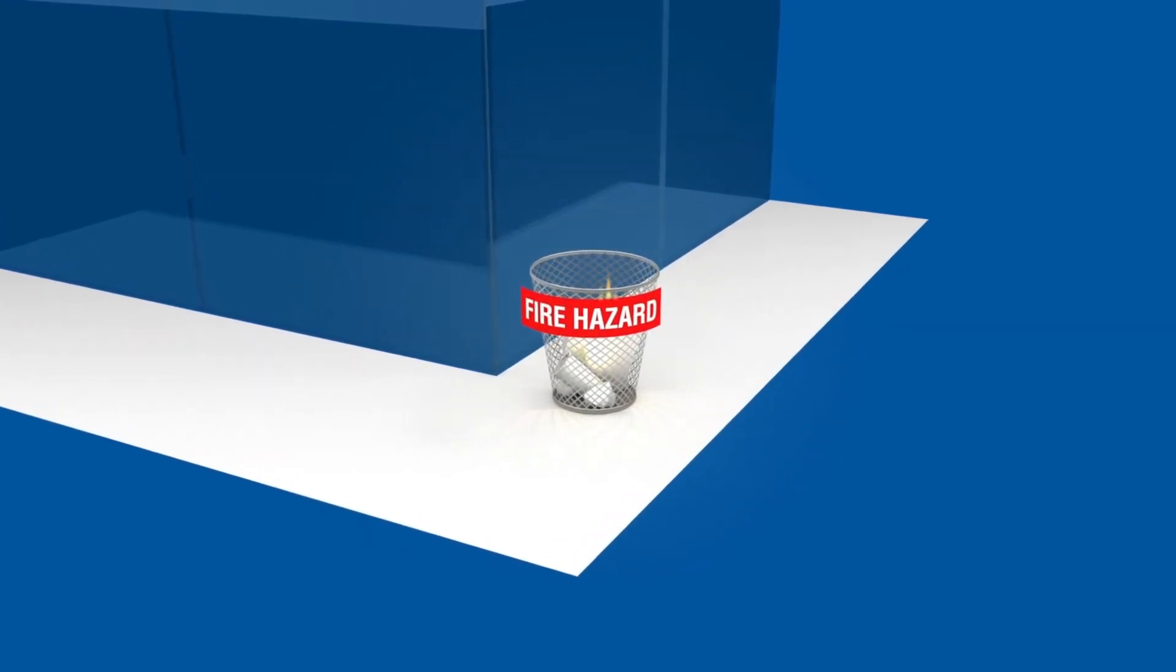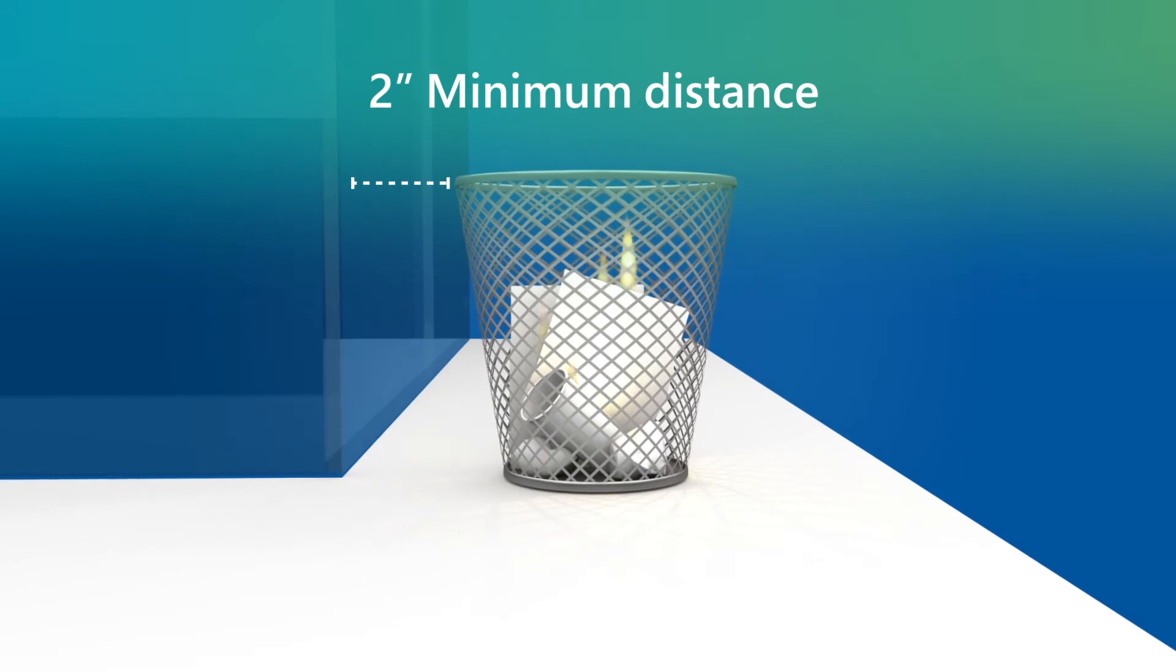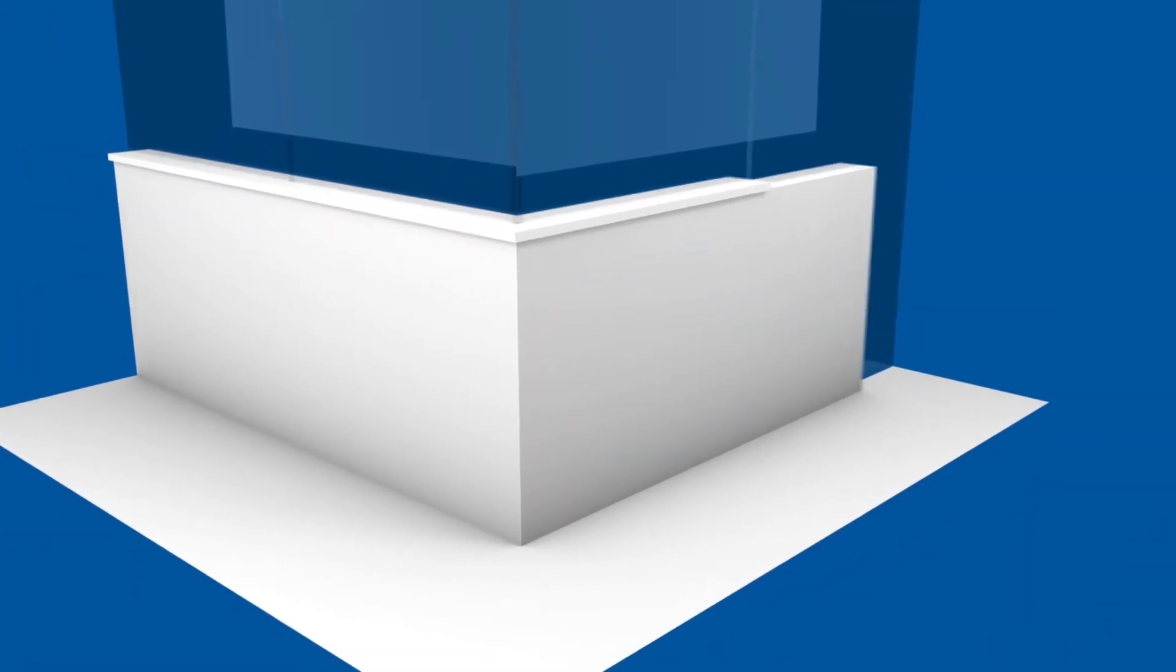Per manufacturer's recommendation, all combustible materials must be kept a minimum of two inches from the face of the glass. You can construct a pony wall using methods and materials based on the type of construction required for the building, as long as it meets the minimum fire resistance rating required by local and state building codes.